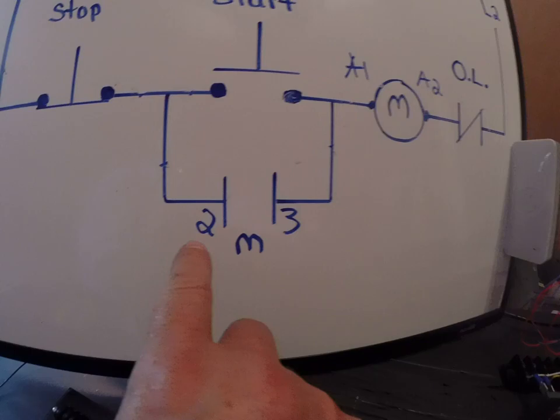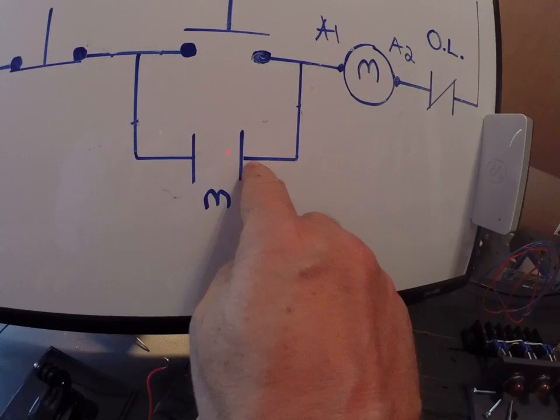So I left this up from yesterday. Remember our holding circuit on the Square D magnetic starter was labeled as 2 and 3? That's not the case. This one actually says the wire numbers are 13 and 14 - that's my holding circuit for this motor starter.